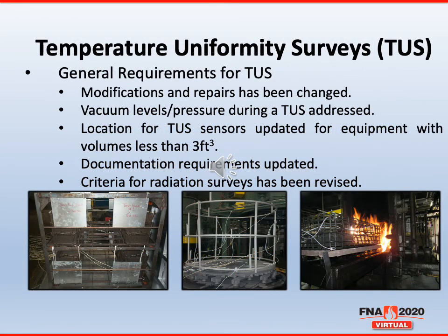Now we're on to temperature uniformity surveys and some of the changes that were addressed in Rev F. We did address modifications and repairs. We've changed up a little bit of the requirements, what defines a modification and repair, and what's supposed to happen after one of those events occurs. We addressed vacuum levels during a TUS. We also defined the location of TUS sensors for volumes of less than 3 cubic feet. We changed some documentation requirements, and also the criteria for radiation test surveys has been revised.